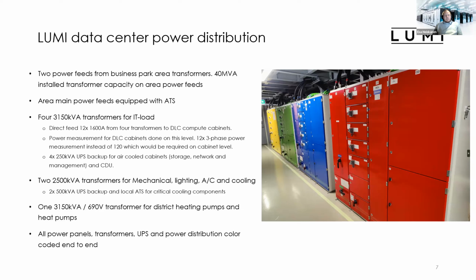Then each of these IT transformers is equipped with a 250 kVA UPS backup, and this is for the air-cooled cabinets, storage, network, and management, and the cooling distribution units on the direct liquid cooled HPC cabinets. We have two 2.5 megawatt transformers for mechanical, lighting, AC, and cooling, and both of these have 500 kVA UPS backup. And also we have local ATSs for the critical cooling components like HPC cooling pumps and all the other critical cooling components. Basically, those are fed from two different UPSs, and the local ATS can transfer the power feed from primary to secondary feed in case of failure.